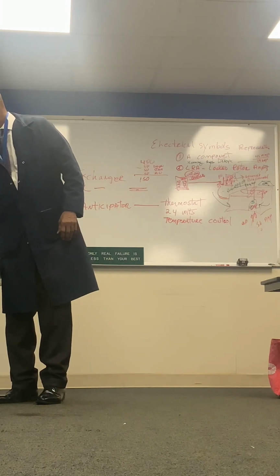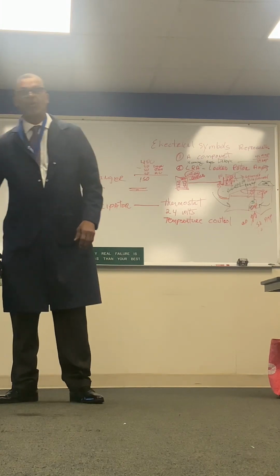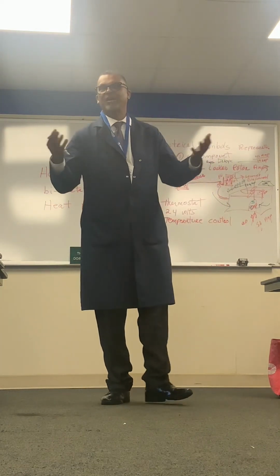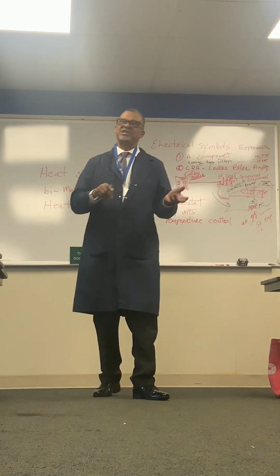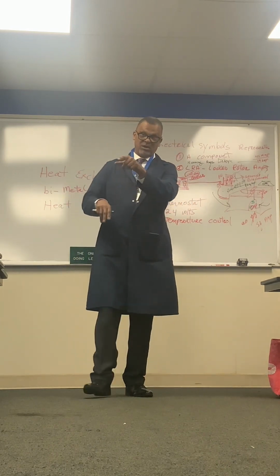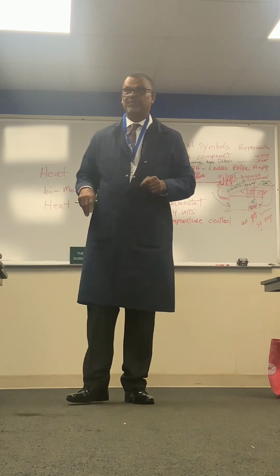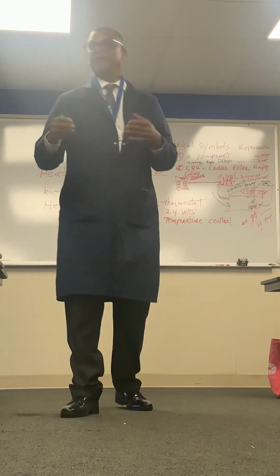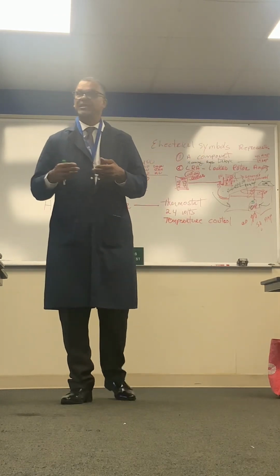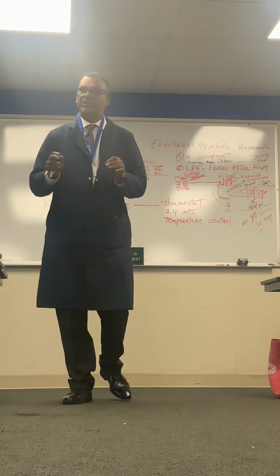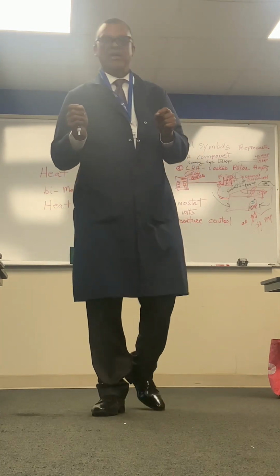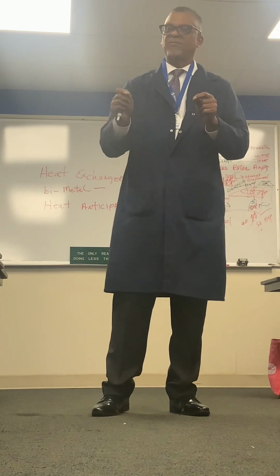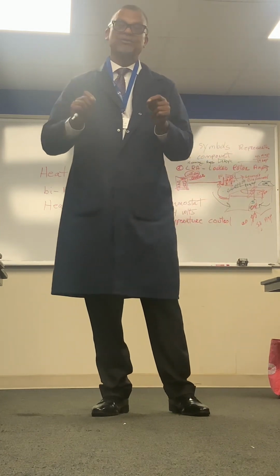Not this motor, because this motor is not a good example. That motor is an electronic ECM motor, the modern type of motor that changes AC to DC. We aren't talking about that yet, but we're going to get there in this book, in this class. An ECM motor is an electronically commutated motor. It changes AC to DC through a process called rectification, which can make DC function like it's 3-phase.